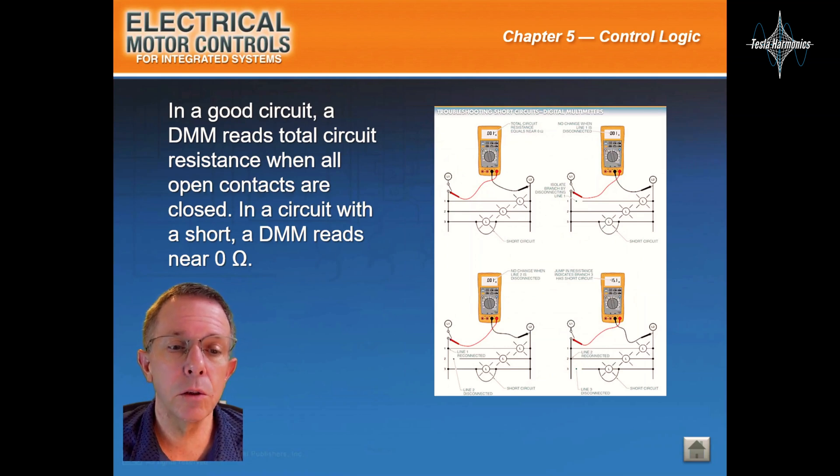In a good circuit, a digital multimeter reads total circuit resistance when all open contacts are closed. In a circuit with a short, a digital multimeter reads near zero.